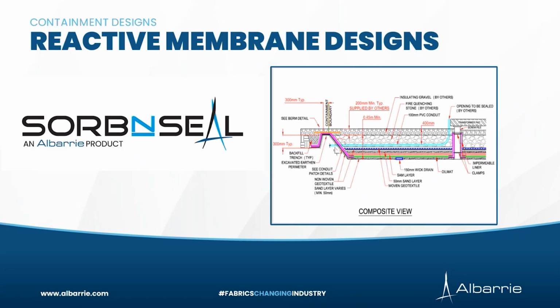SorbNSeal, formerly SorbWeb, is an earthen berm style containment designed to be completely below grade and maintenance free. The floor area of the containment is the oil-blocking fabric shown in the first video, shown here as the green line. Over top of that is the super absorbent membrane, which manages any chronic leaks that could happen over the lifetime of the containment, shown here as the red hatching, the same white fabric shown in the second video. There are a few other layers I'll get into later, but basically you have an earthen berm, usually built or excavated on native soil.